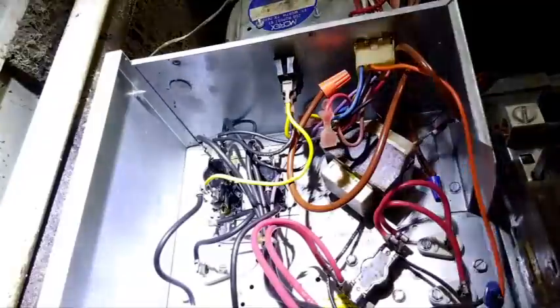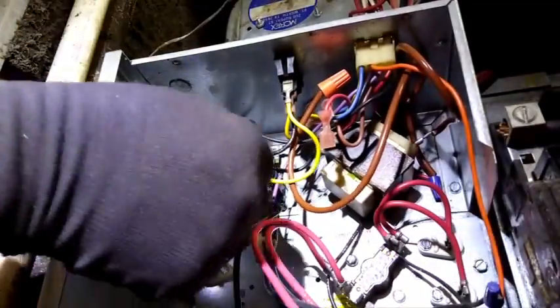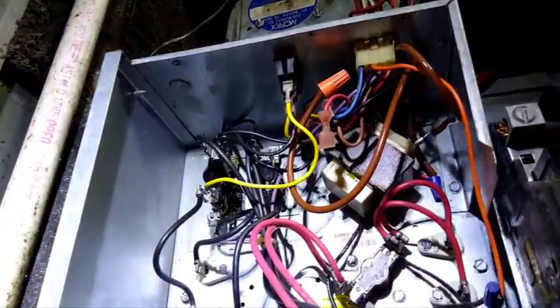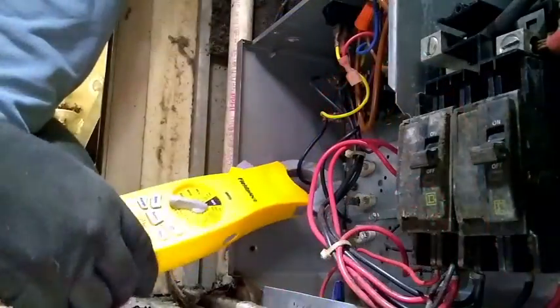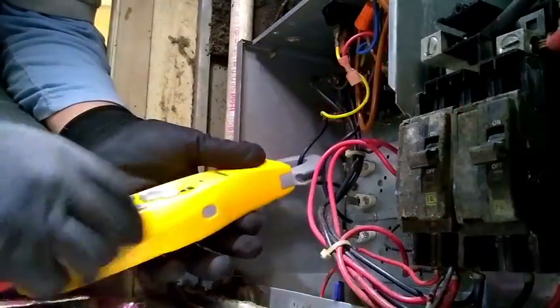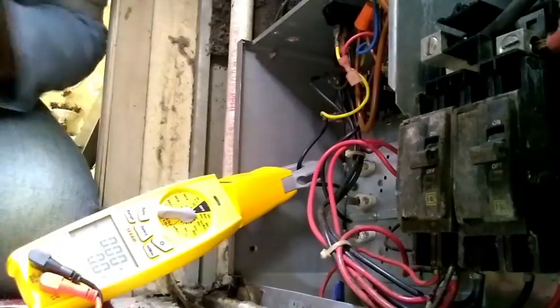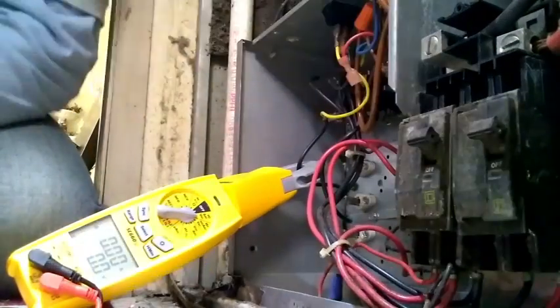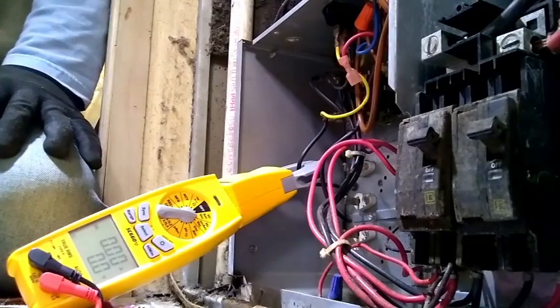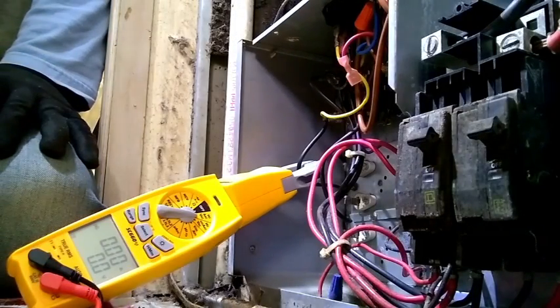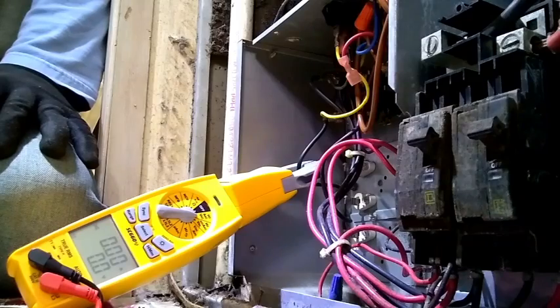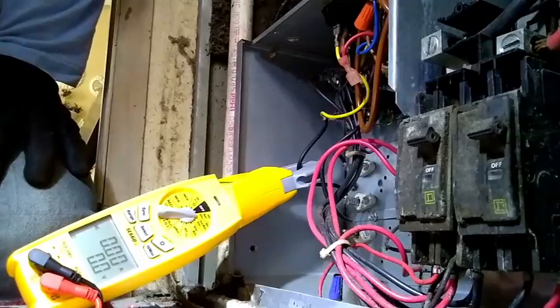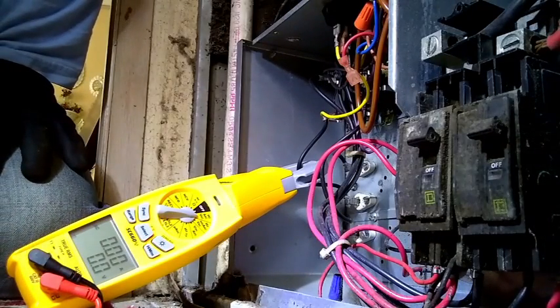Double checking all the wires, as you can see, just kind of moving around there, make sure nothing's loose, because what's going to happen when one gets loose, it'll burn off the next day. It never fails, so make sure you check that. There's a thumbs up of success. We're going to turn it back on here, and we should see it pull 20 amps, and the blower should come on. Here it is.